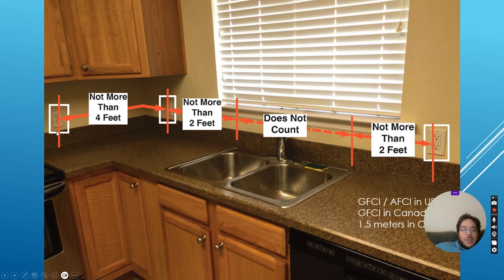So the other rule is, in both Canada and the US, we have to have at least 2 separate circuits for the kitchen countertop receptacles, and no more than 2 receptacles per circuit. So if you look here, we could have 1 circuit for this receptacle and 1 circuit for these 2 receptacles. So I need a minimum of 2 circuits, but probably more. And if I got 5 receptacles, that means I need 3 circuits. If I've got 7 receptacles, that means I need 4 circuits. You know, does that make sense?